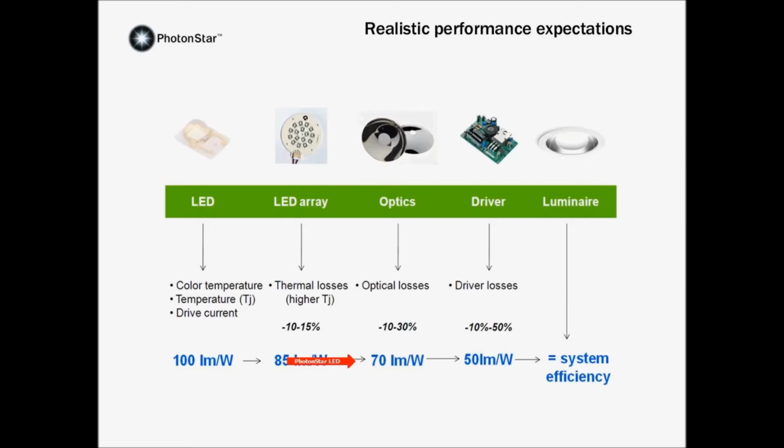So when you multiply all that together, you get whole luminaire system efficiency. My rule of thumb is that for economically sensible things, it's about 2/3. So if you've got an LED number there at 100, you'd be expecting 66 out. If you look at the 2013 catalogue, we've got lumen LED efficiency numbers in the 130s, so we'd be expecting above 90 lumens per circuit watt for those.